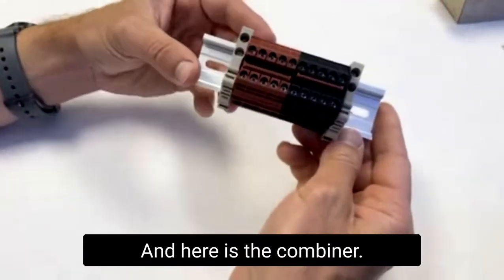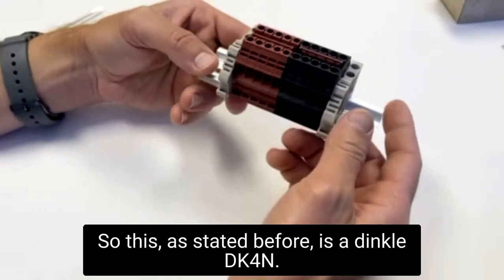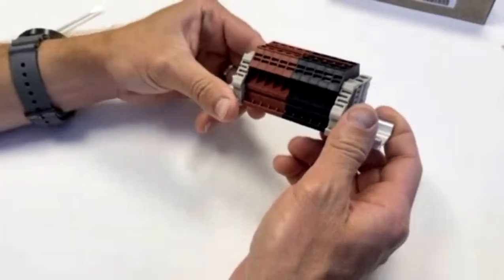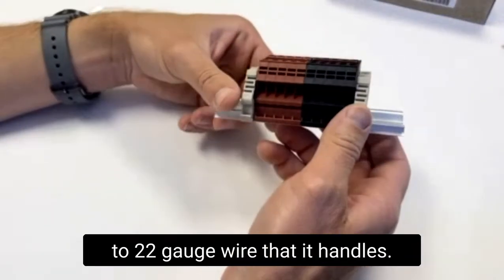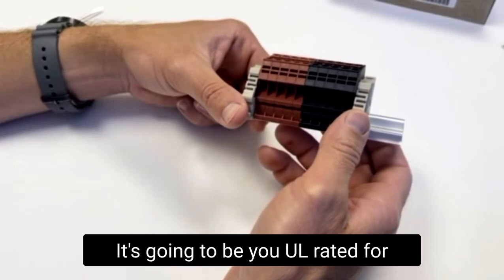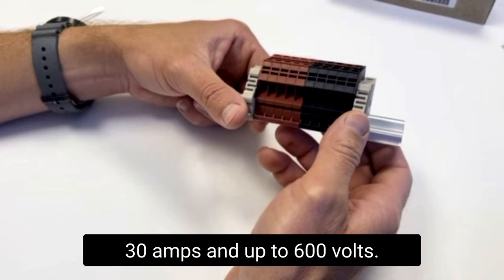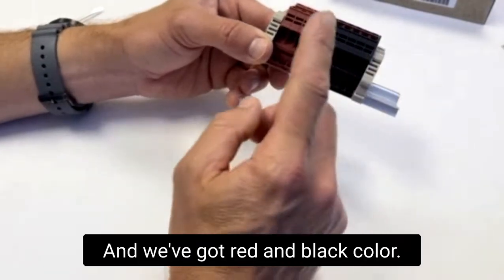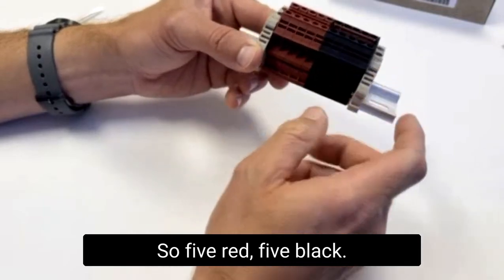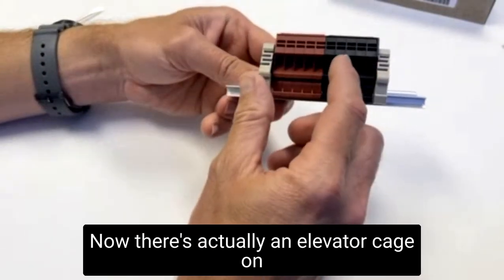Here is the combiner. This is a Dinkle DK4N. It handles 10 to 22 gauge wire, it's UL rated for 30 amps and up to 600 volts. We've got red and black colors, five red, five black. There's actually an elevator cage.